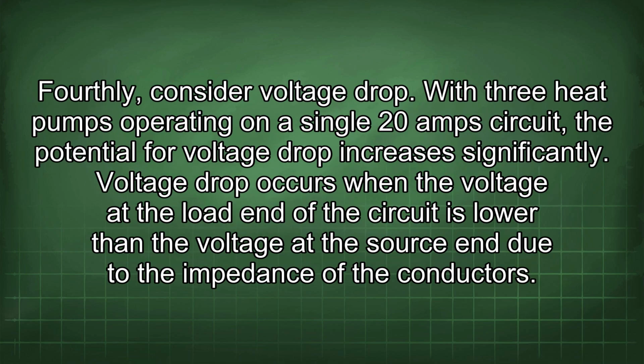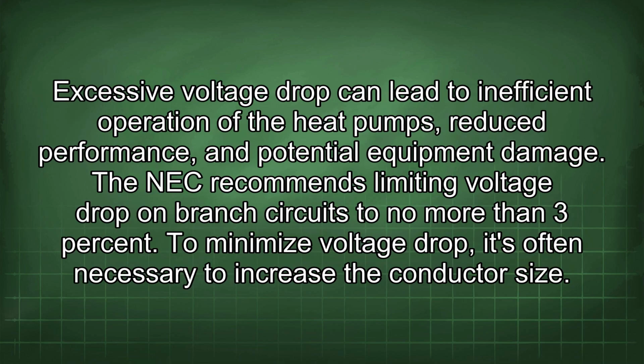Fourthly, consider voltage drop. With 3 heat pumps operating on a single 20 amp circuit, the potential for voltage drop increases significantly. Voltage drop occurs when the voltage at the load end of the circuit is lower than the voltage at the source end due to the impedance of the conductors. Excessive voltage drop can lead to inefficient operation of the heat pumps, reduced performance, and potential equipment damage. The NEC recommends limiting voltage drop on branch circuits to no more than 3%.